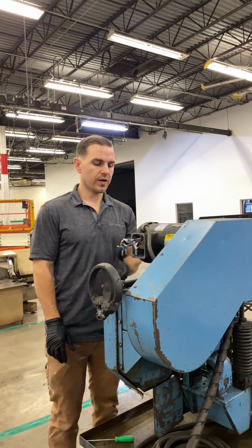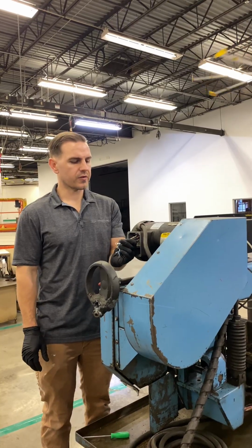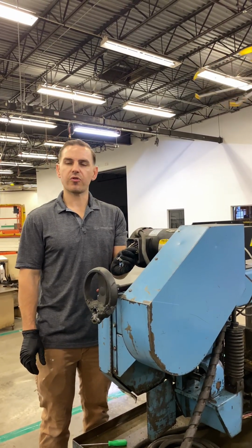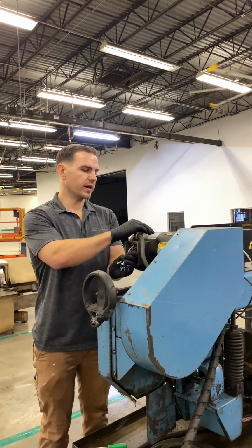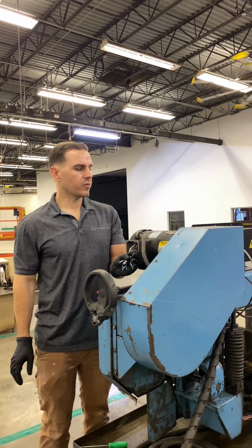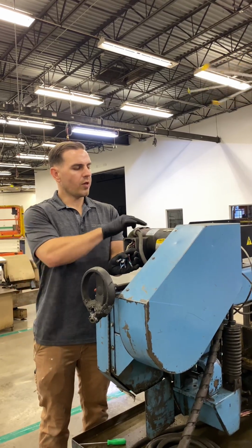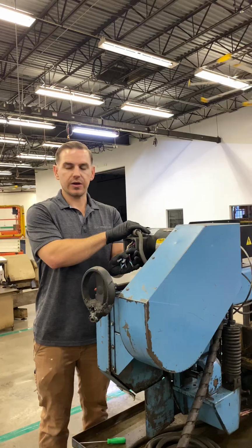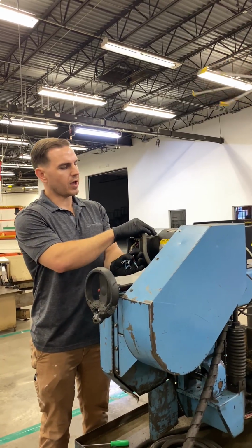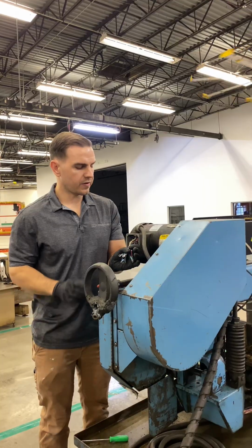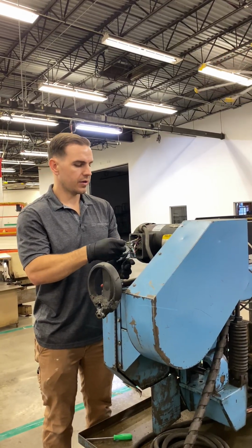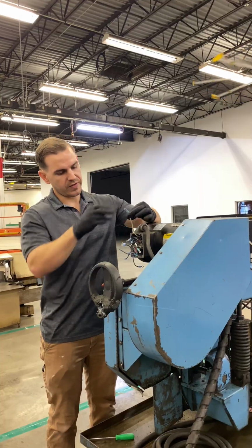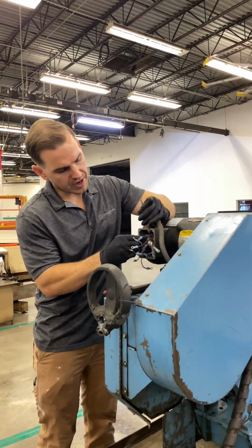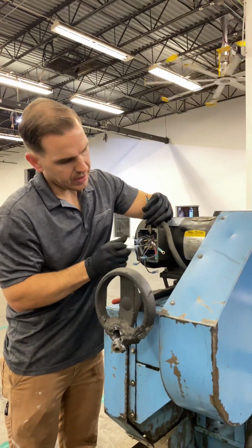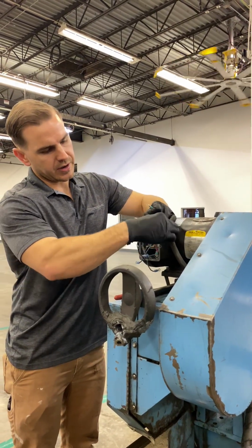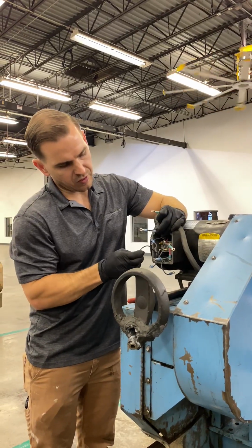Okay guys, we have all of our wires pulled out of our terminal box. So remember, we're switching over to 480 volts, so I'm going to be using the guide on the right side. And the easiest way to do this is go one line at a time and go across line 1, line 2, line 3. So right now it's saying line 1 is going to go to wire number 1. So I'm going to take my line 1, I'm going to find wire number 1, and you can see here that they're labeled on the wires.